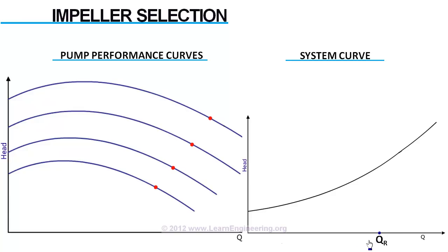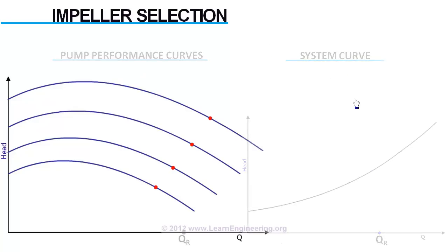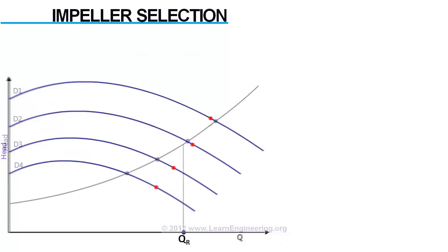The operating point of the pump will be the intersection point of system curve and pump performance curve. So, depending upon selection of impeller, the pump could operate anywhere here. But, we have a requirement of specified flow rate. Out of these operating points, this is the one which is most near to the required flow rate. So, we will select this impeller.